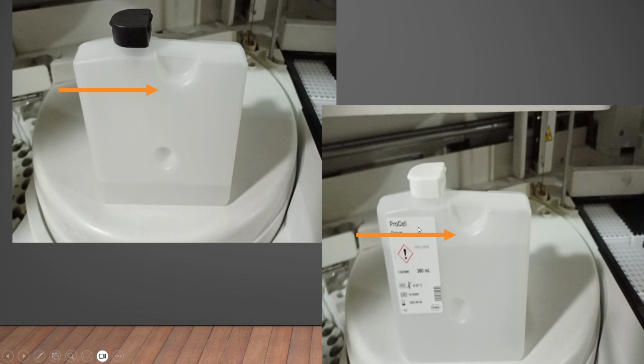Okay, so whenever you are placing these procell and clean cell, make sure that the liquid level is always at or below this crescent shaped area. Okay, when the new one comes, it is always slightly on the higher side. So when you put a new procell clean cell into the instrument, there is a possibility that it may give an alarm and stop. Because of that reason, you have to ensure that the liquid levels are always at or below this crescent shape.